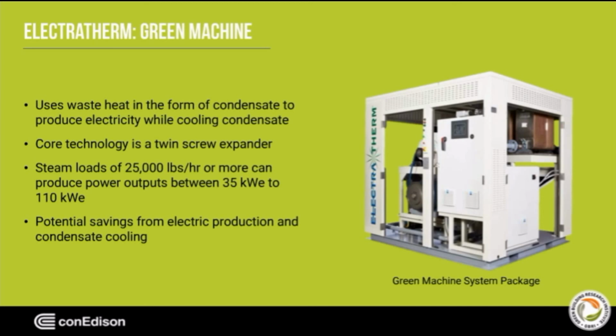Most of our customers currently are cooling the condensate and then releasing it to the sewer. This system utilizes hot water to produce power between 35 kW and 110 kW, depending on the hot water flow rate. Customers will be able to benefit from savings from the electric production as well as from water savings.